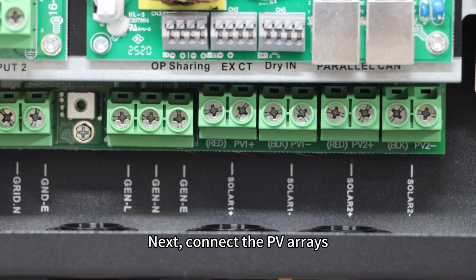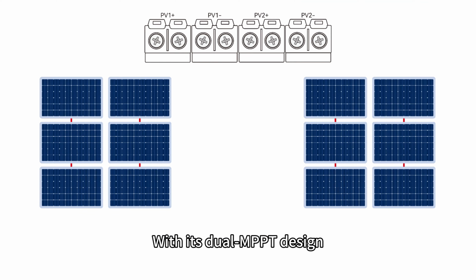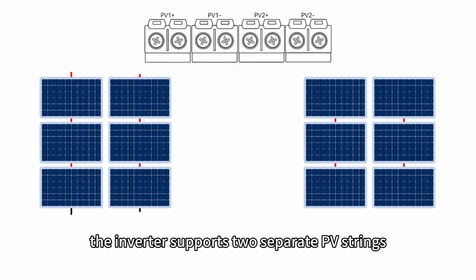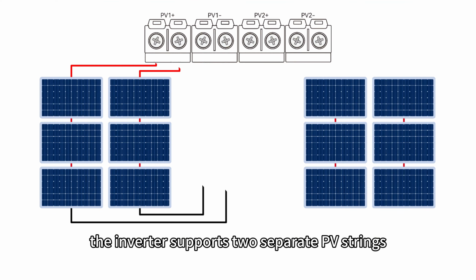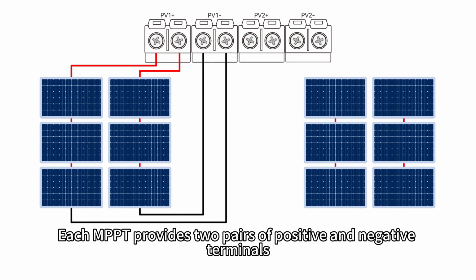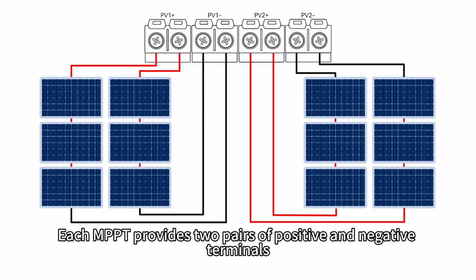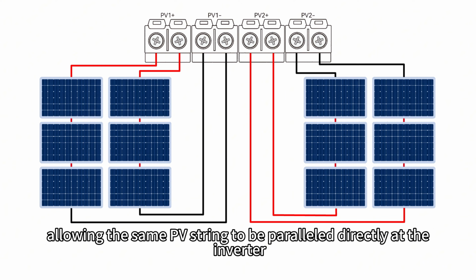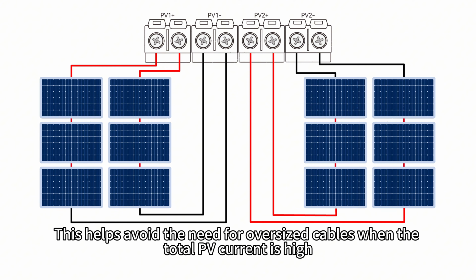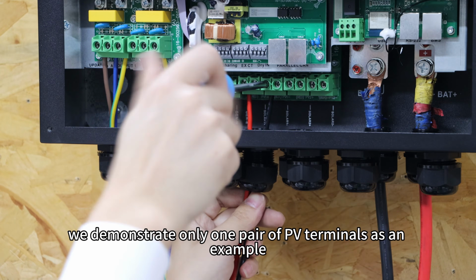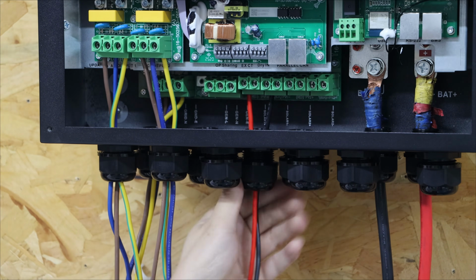Next, connect the PV. With its dual MPPT design, the inverter supports two separate PV strings. Each MPPT provides two pairs of positive and negative terminals, allowing the same PV strings to be paralleled directly at the inverter. This helps avoid the need for oversized cables when the total PV current is high. Here we demonstrate only one pair of PV terminals as an example.